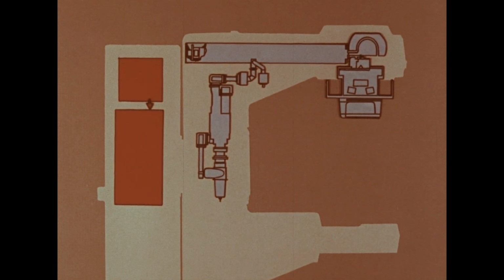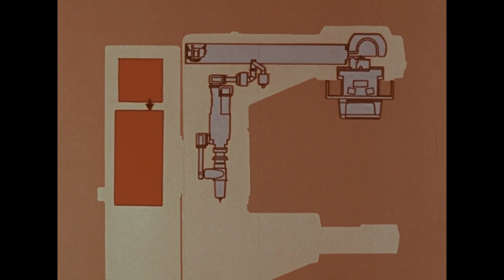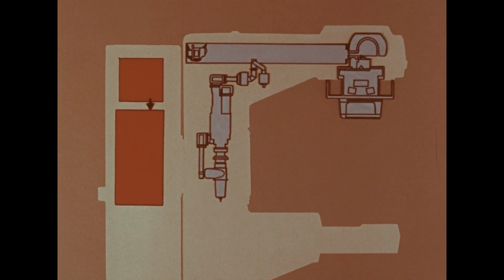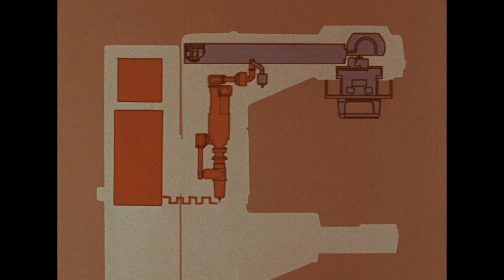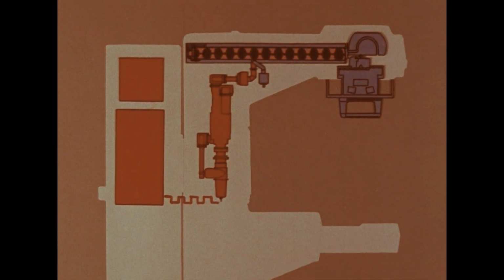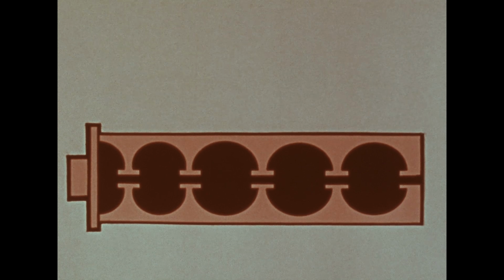They work like this. The power supply provides a high voltage power to the modulator, which converts the direct current to high energy pulses. These pulses drive the microwave power source, which is a high power amplifier tube. Pulses of microwave frequency power from the tube are coupled to the acceleration waveguide designed to build up a standing microwave field. Electrons are shot into this field by the electron gun, a heated cathode with a Pierce focusing device.